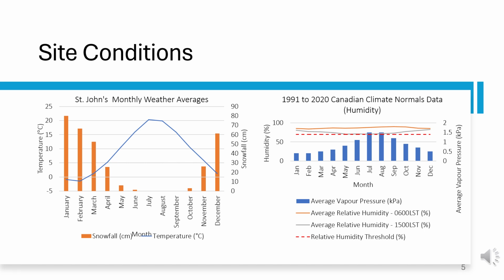Now, to maintain safe operating conditions for the IT equipment, St. John's is actually a good weather and a good location for this. For most of the year, the relative humidity hovers below or near the 70% threshold, and this supports the ASHRAE standard and confirms that air cooling is viable for long periods, and we can use the winter air to actually cool our system and in turn reduce the energy consumption.